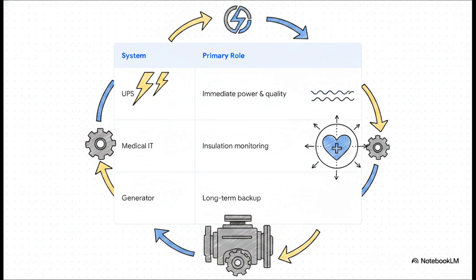Take a look at this table. It breaks down the distinct roles of your main power defenses. The UPS provides immediate power maintenance and cleans up power quality. The medical IT system, specifically the isolation transformers, provides insulation monitoring to protect patients from microshocks on a first ground fault. And your generators, that's your long-term heavy-duty backup. The key takeaway here is that they solve entirely different problems. They cannot replace each other, they have to work together in harmony.